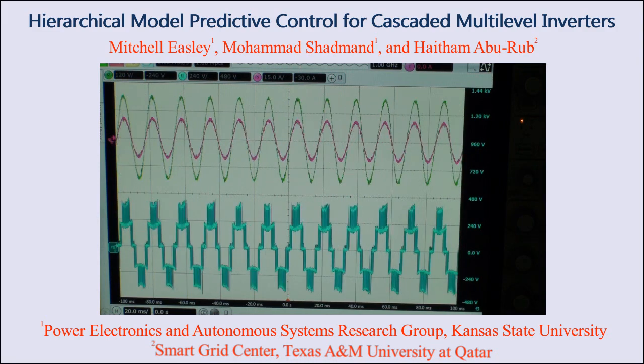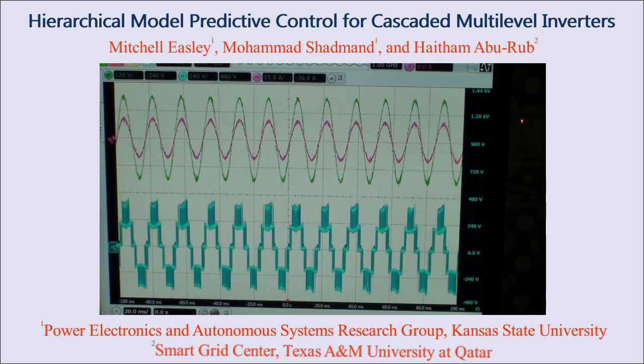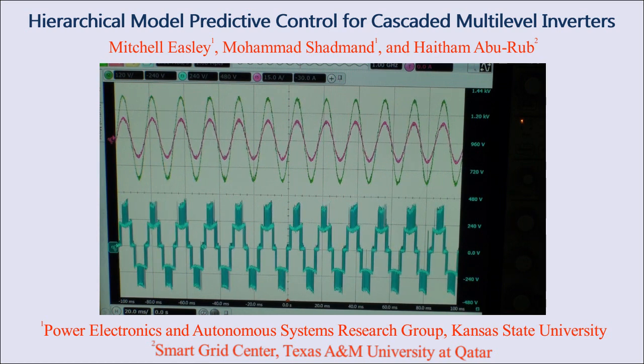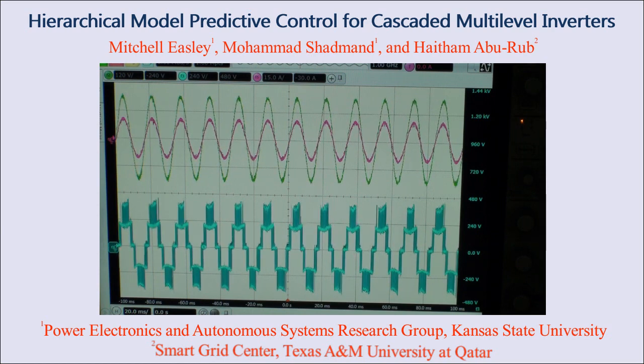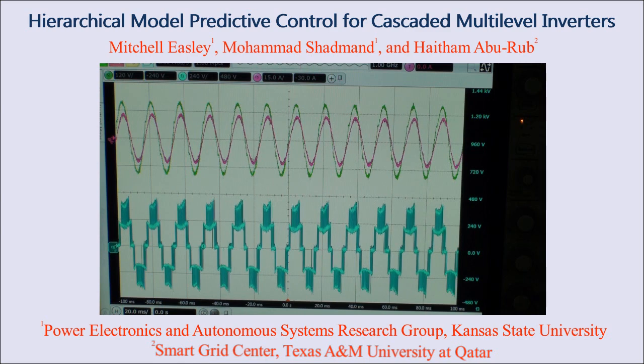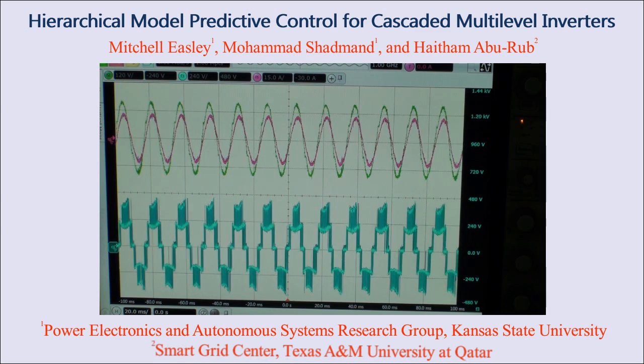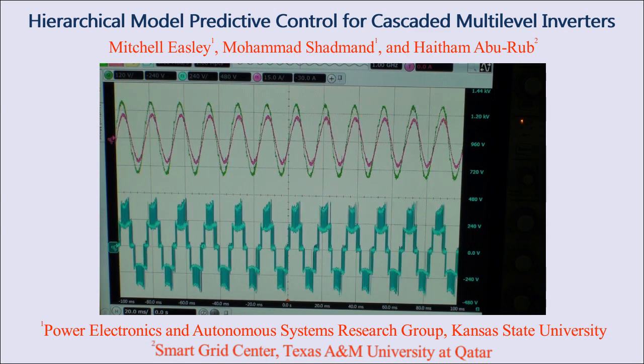The power reference is reset to 1 kilowatt. In the case of significant grid voltage sags, the controller is programmed to inject 250 VAR while maintaining the power reference. The reactive power injection is evidenced by the leading grid voltage.